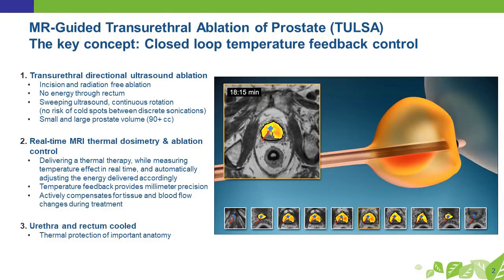The key concept of TULSA that makes it really unique is closed-loop temperature feedback control. The technology takes advantage of the real-time MR mapping. That means that as the ultrasound energy is delivered, the temperature in the tissue is mapped out by the MRI and fed back, and this controls the amount of energy and the duration of energy that's delivered by the transducer.